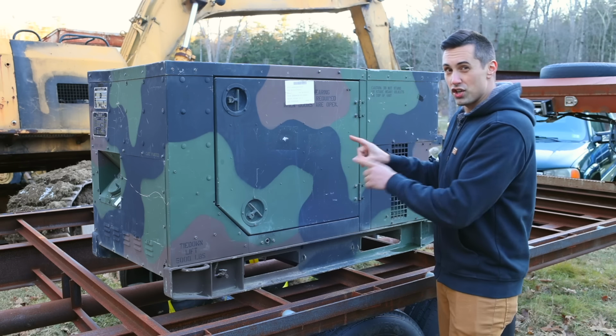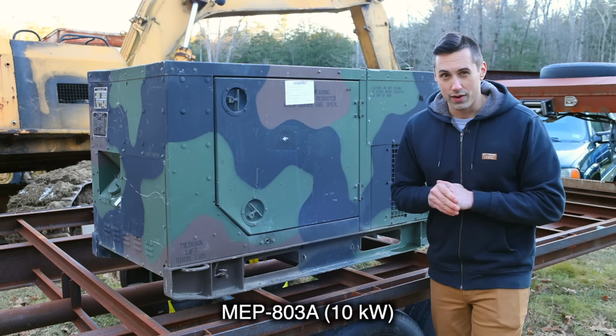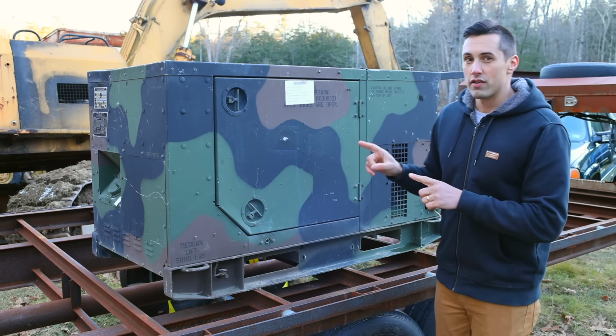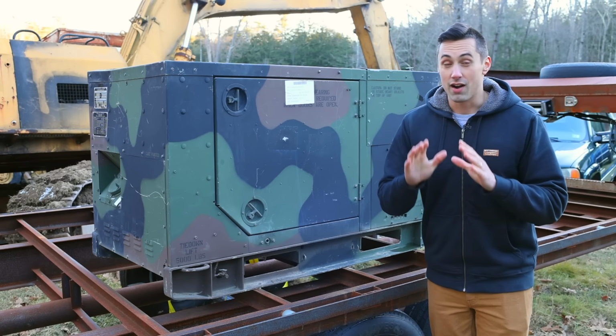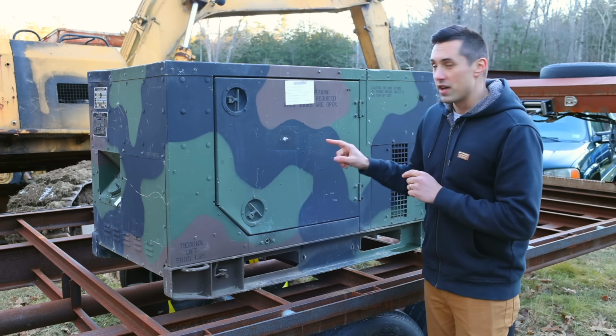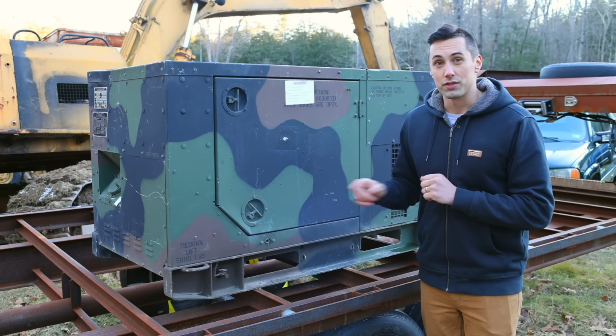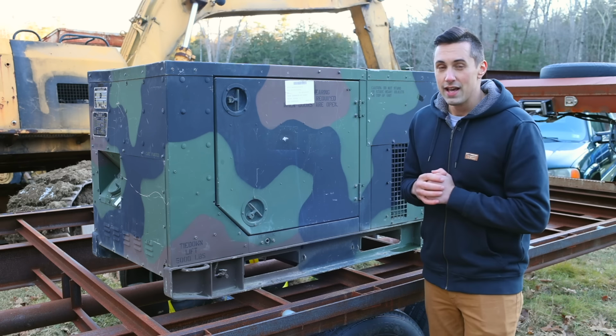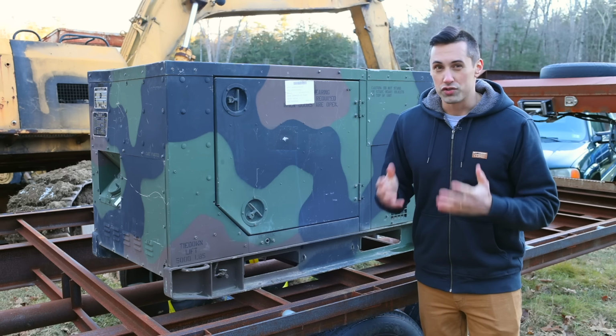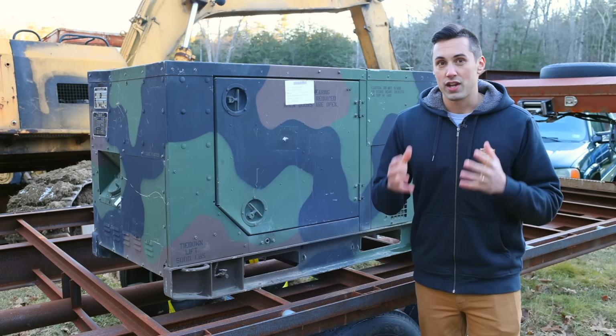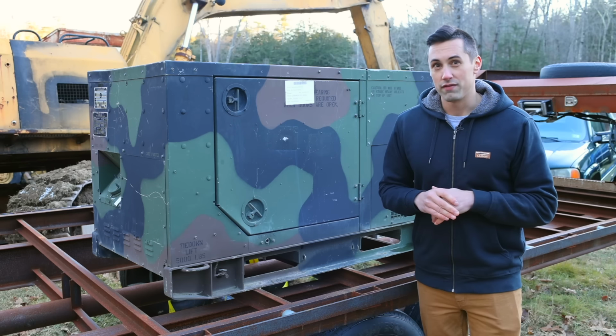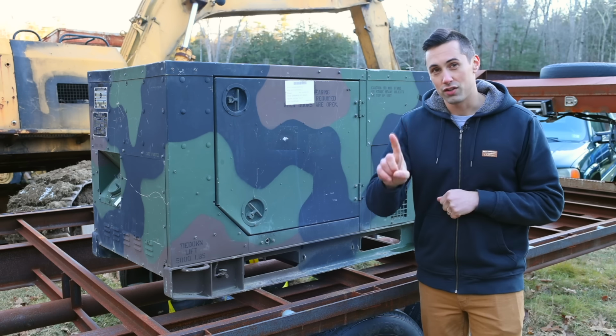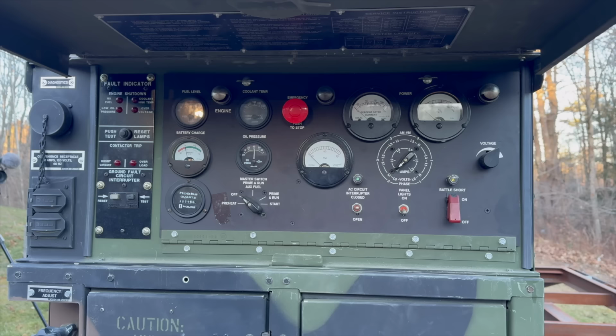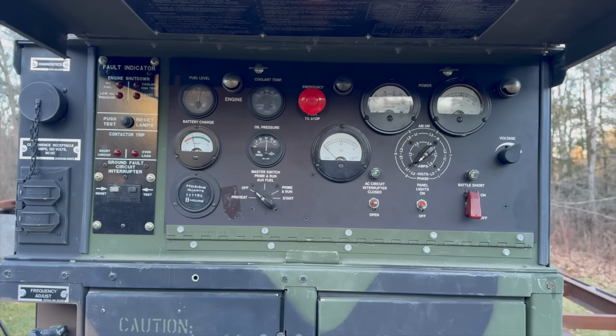Now, the model of this generator is an MEP 803A. If you're looking to buy one of these generators, be very careful because there are some pitfalls, especially when you get into the larger capacity generators. Many of them are 3-phase only, and many of them operate at 400 hertz. If you're going to power a house in the US, you need a 240 volt generator that operates on single phase and 60 hertz. Now, the auction listing claims this generator operates.